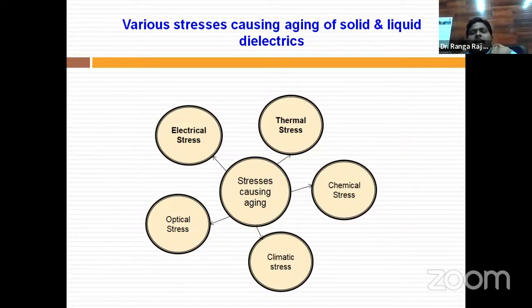This is a very, very dangerous situation in any electrical machine. So we should reduce the temperature with some cooling system or other technologies. Otherwise, the material loses its properties. If insulation fails, the whole machine gets burned, which leads to a huge loss to the utility as well as the customer. So thermal stress is the major stress.